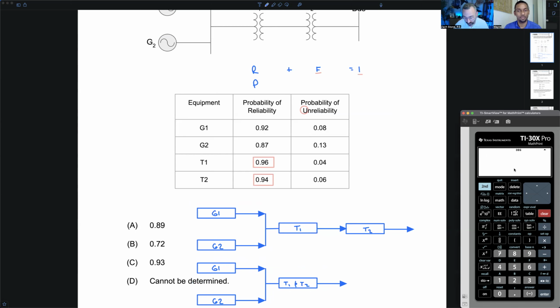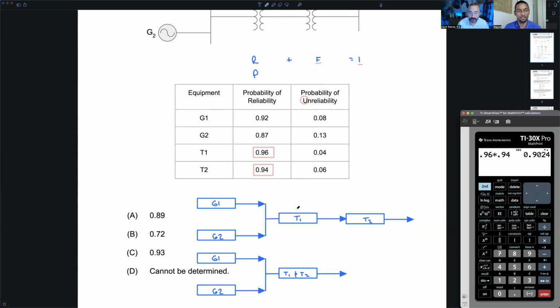Probability of reliability for transformer one is 0.96 times the probability of reliability for transformer number two, 0.94. That means, combined into their equivalent single block, this block has a probability of 0.9024, or about 90%. Are you with me so far? Yes, I am.